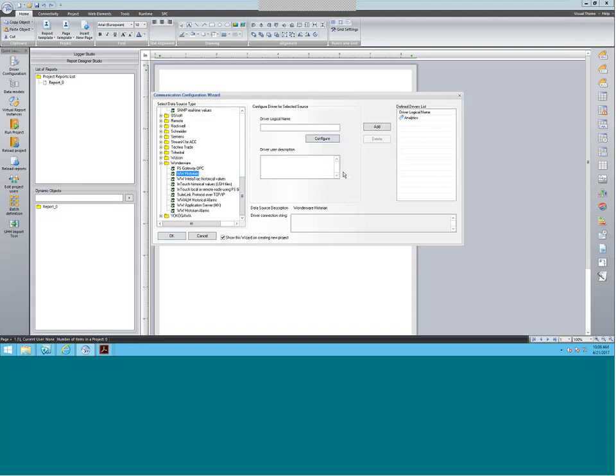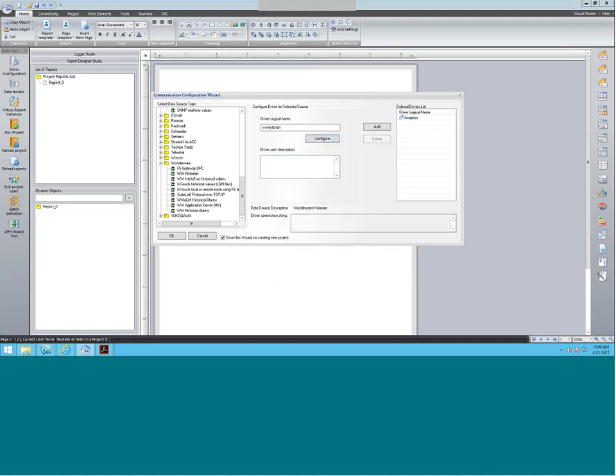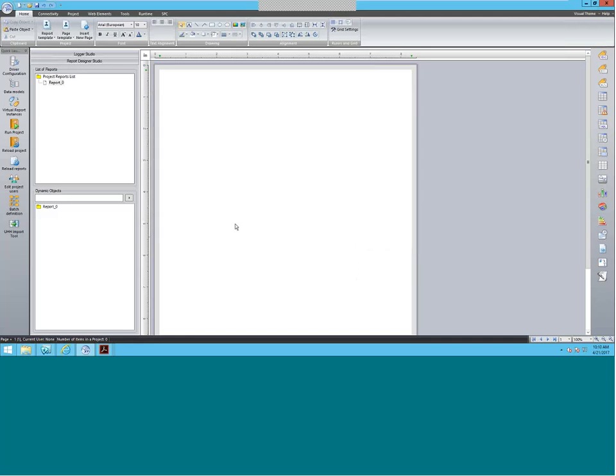We've been storing data for the better part of this morning, so we'll be able to use some of that data to make a report. First thing is to give a driver a name — I'm going to call it WHistorian. Configuring the driver, you can connect to the historian in different locations if you go to a remote computer. Our historian is actually located on the local computer here. Test out the authentication — you get a test connection succeeded. Click OK and then add to add the historian. Once you define a driver and put it in here with the right ports and data source, you can use it continuously over the report.